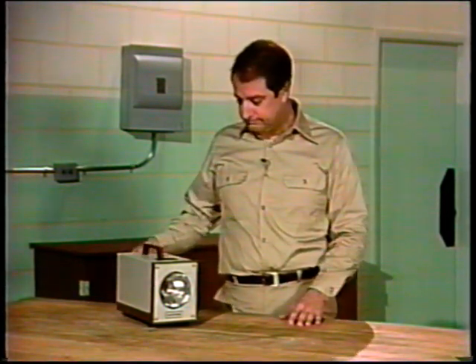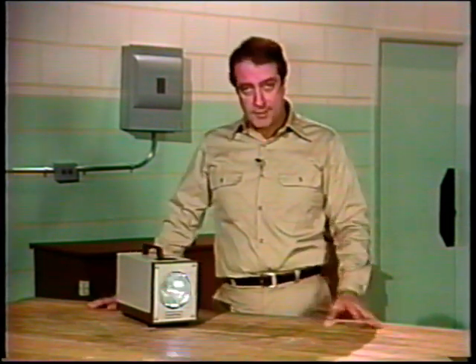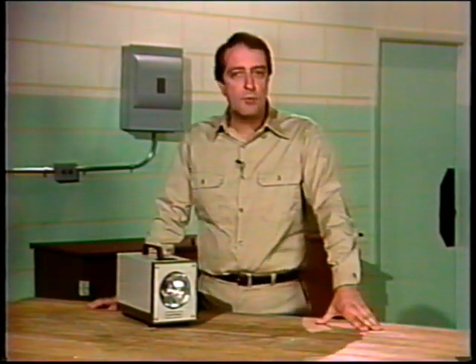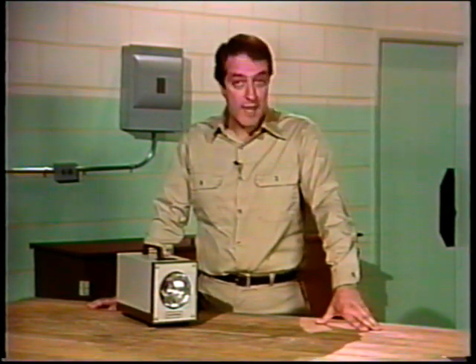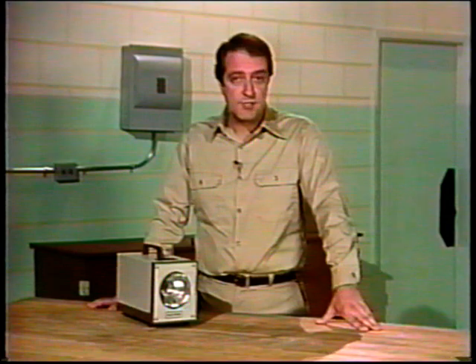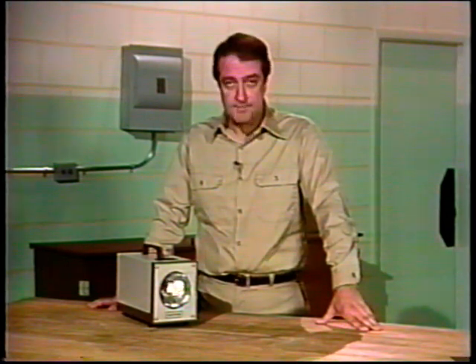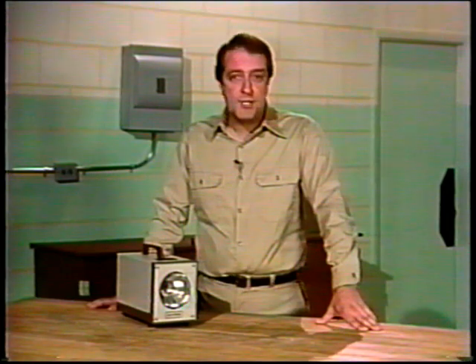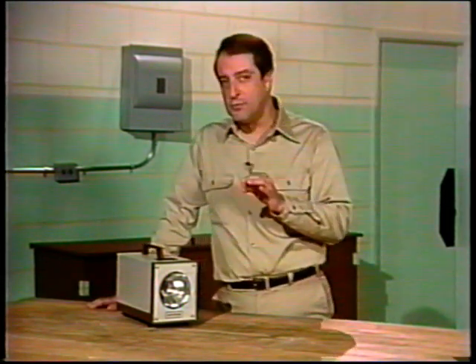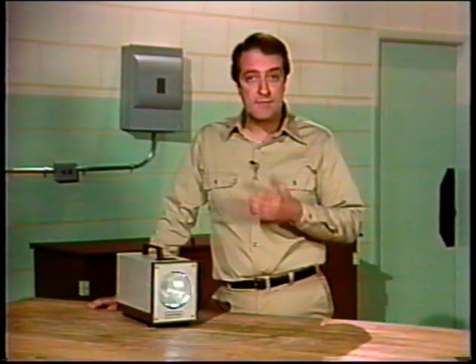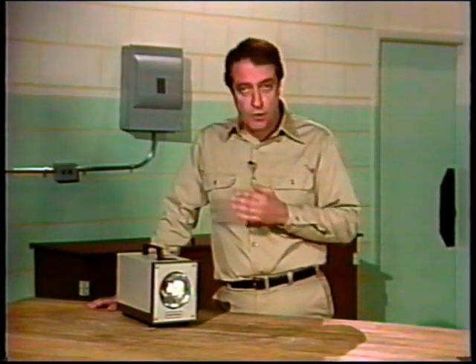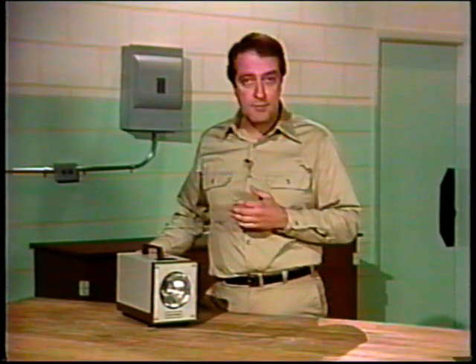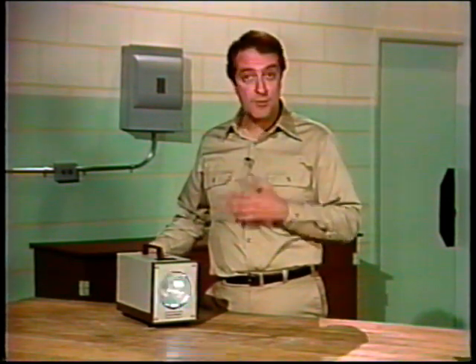We can demonstrate this effect of load on a synchronous motor by using a strobe tachometer. A strobe tachometer is an instrument that allows the speed of a rotating piece of equipment to be measured without touching the shaft. You may already have seen the effects of a strobe light on moving objects. If you have, you've seen how the flashing of a strobe light appears to stop the action for a moment. Well, a strobe tachometer gives a similar effect. It uses a strobe light and has a dial to adjust the number of times the light flashes in a minute to the number of rotations per minute of the equipment being measured.